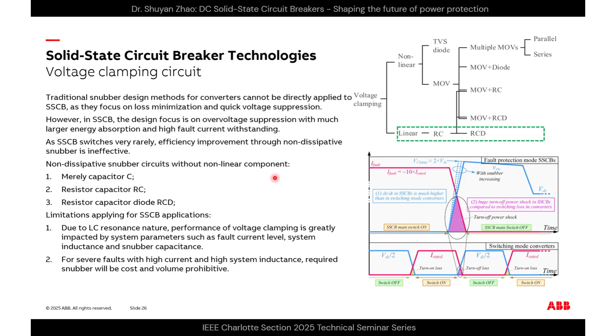And a more common clamping solution is by using those metal oxide varistors. We call it MOV. And the fundamental operating principle of MOV is the change of resistance as a function of applied voltage. So during the solid state breaker turn-off process, like here, the voltage and current, once the clamping voltage is reached, like here, the voltage across the MOV remains fairly constant, with a progressive decrease in current as energy stored in the system inductance is dissipated in the MOV. And compared to snubber circuits, like the blue waveform here, the voltage clamping circuit based on MOV has the benefit that clamping voltage performance is fairly decoupled from system parameters like current or inductance, which ensures a more general solution, which means one solution can fit a wider range of system parameters.